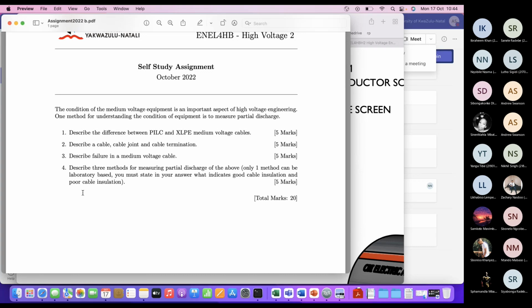You could also have some sort of RF antenna to see if you could locate a partial discharge. What was important here is that it must be focused on the cable. I didn't like it when folk put a UHF antenna into a transformer and were indicating that was a method to measure partial discharge in a cable. That doesn't sit nicely. All right, you must state in your answer what indicates good cable insulation and poor cable insulation.